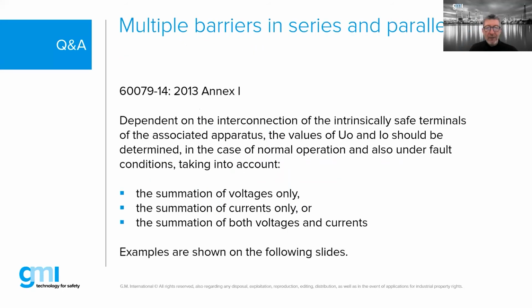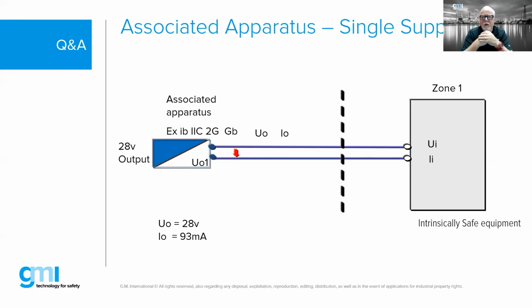Here we go, so we have an associated apparatus, and on the right-hand side, our intrinsically safe equipment. Our associated apparatus is designed with an output of 28 volts, providing 93 milliamps of power going through this device. We need to check our input on the intrinsically safe equipment on the right-hand side, to make sure we don't exceed its maximum parameters. For example, the output may be 28 volts from our associated apparatus, while our device may say the maximum input it can take is 30 volts, so we're below that and that's okay. There's a whole bunch of these checks we take into account, what we call entity parameters.